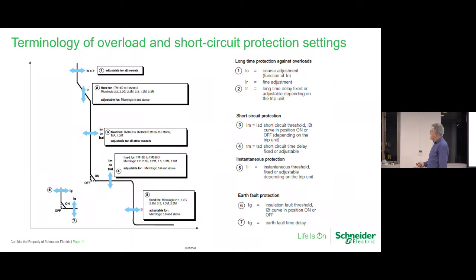Short circuit protection, IM, is also known as ISD. So IM is magnetic protection. There are different types of trip units, and we'll talk about that in a minute. But the area there is often the IM and ISD settings are the ones that are often not set correctly.